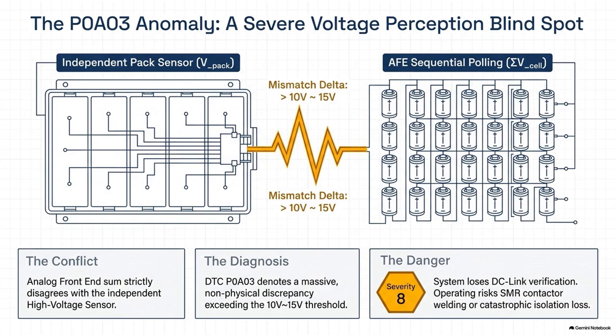Yeah. You can't just pipe 800 volts of raw power directly into a fragile silicon microchip to measure it, right? You could just explode. You absolutely cannot. The analog to digital converters on those chips can only handle about 3 to 5 volts. So how do they do it? Well, the engineers use a series of mega-ohm divider resistors to step that massive 800-volt potential down to a safe, readable level. So a mega ohm resistor is basically providing a massive amount of electrical friction to drop the voltage. Exactly. But these resistors are precision components. Their accuracy is highly dependent on their material properties, often a specific carbon or metal oxide film.